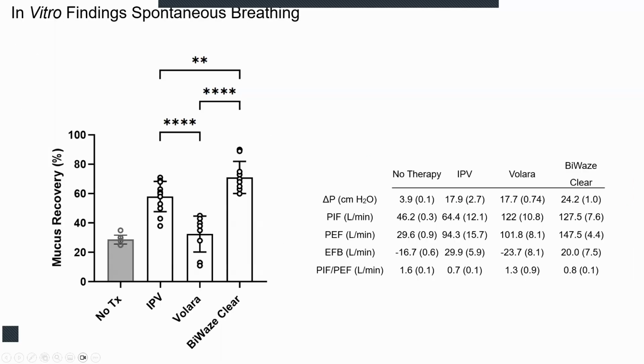What I wanted to show you is that even during normal tidal breathing in this model with the 3D printed airway and the pig lungs attached, we're getting approximately 30% of the mucus out. That's with the model at essentially 0 degrees, so we're not angling it at all. With gravity dependence, we'll see much more coming out, but it's really flow that predicts how much of the secretions come out, along with the delta pressures, the timing of those delta pressures, and the effect that has on the flow.